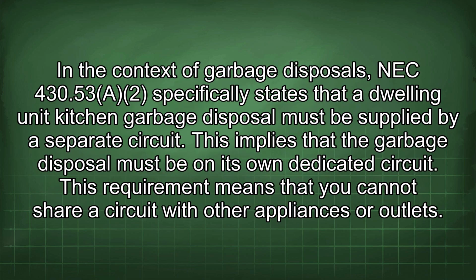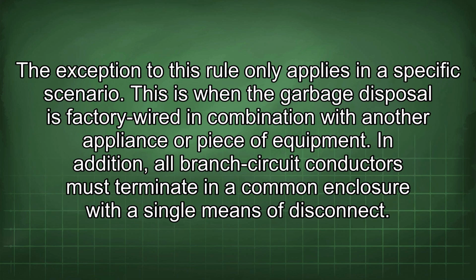In the context of garbage disposals, NEC 430.53(A)(2) specifically states that a dwelling unit kitchen garbage disposal must be supplied by a separate circuit. This implies that the garbage disposal must be on its own dedicated circuit. This requirement means that you cannot share a circuit with other appliances or outlets. The exception to this rule only applies in a specific scenario. This is when the garbage disposal is factory wired in combination with another appliance or piece of equipment. In addition, all branch circuit conductors must terminate in a common enclosure with a single means of disconnect.